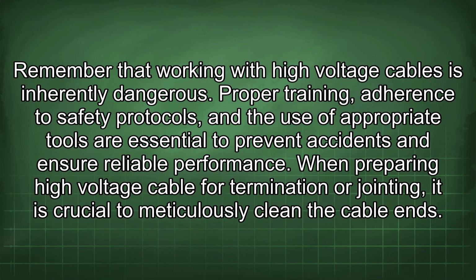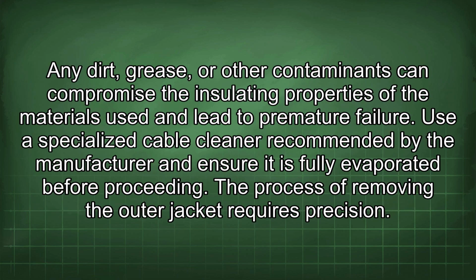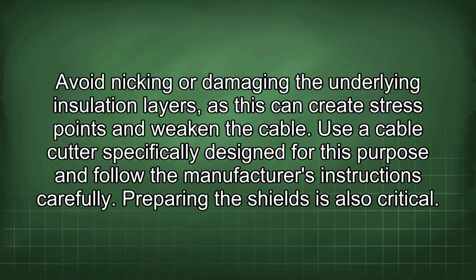When preparing high voltage cable for termination or jointing, it is crucial to meticulously clean the cable ends. Any dirt, grease, or other contaminants can compromise the insulating properties of the materials used and lead to premature failure. Use the specialized cable cleaner recommended by the manufacturer and ensure it is fully evaporated before proceeding. The process of removing the outer jacket requires precision. Avoid nicking or damaging the underlying insulation layers, as this can create stress points and weaken the cable.